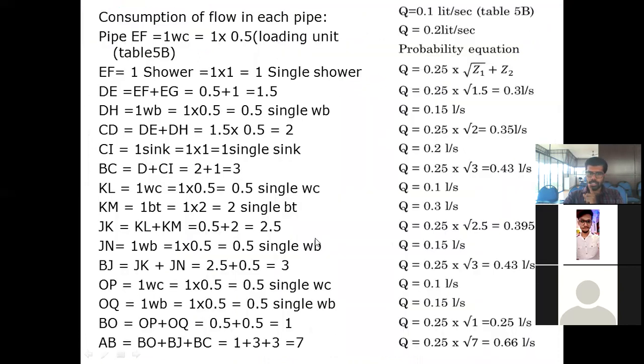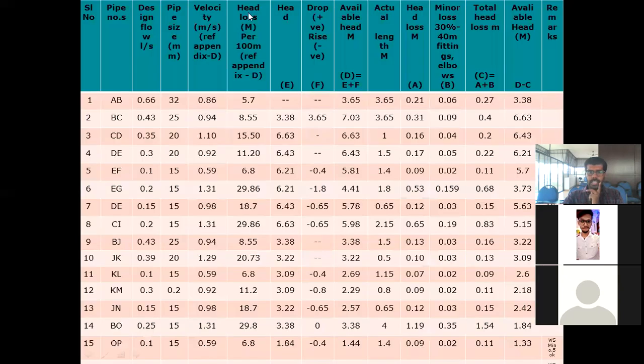Okay. So here I have written head loss in meter per 100 meter only, so 57 will become 5.7. That's the difference. We can write here 1000, then you can write here 57. Whatever you want to write, you can write it here. So if you write 1000, you write 57.02. You are getting what I am saying, right? This is what you will be getting from the Hazen-Williams table.